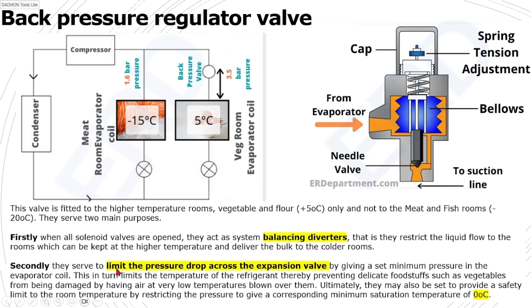Secondly, it serves to limit the pressure drop across the expansion valve, or to define a minimum saturation temperature at the evaporator — normally 0 degrees Celsius. These are the two main purposes of the back pressure regulating valve. I hope you have understood what the back pressure valve is, its application, and how it is set. Stay tuned and I will be explaining refrigerants and other parts, as well as air conditioning, in my next videos. Thank you.